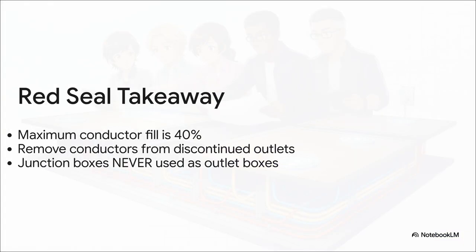To summarize our entire explainer today, here is your Red Seal takeaway. These are the 3 absolute most important things to lock in for your exam and your career. Number 1. Maximum conductor fill is 40%, but always watch out for those jacketed cable exceptions. Number 2. Always physically remove insulated conductors from discontinued underfloor outlets. Don't leave them in there. And number 3. Junction boxes in these underfloor systems can never, ever be used as outlet boxes.